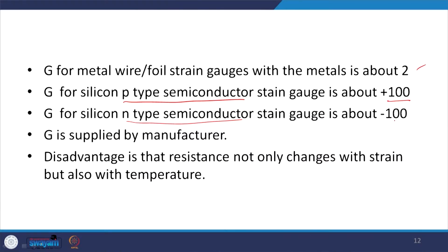The gauge factor G for metal wire or foil strain gauges is about 2, whereas G for silicon P-type semiconductor strain gauges is about +100, and for N-type semiconductor strain gauges G is around -100. This G value is usually supplied by the manufacturer. A disadvantage of strain gauges is that resistance changes not only due to strain but also with temperature, so we must always keep this factor in mind and work to eliminate the resistance change caused by temperature.